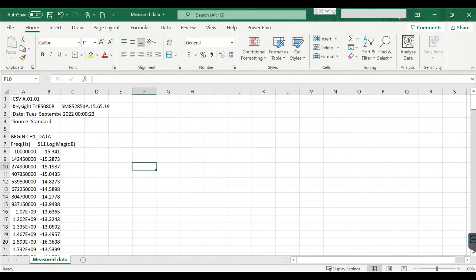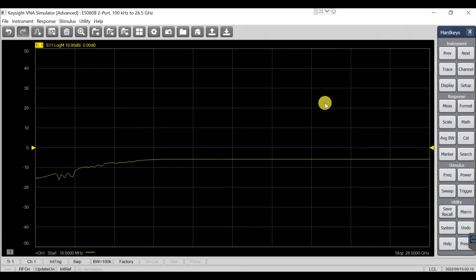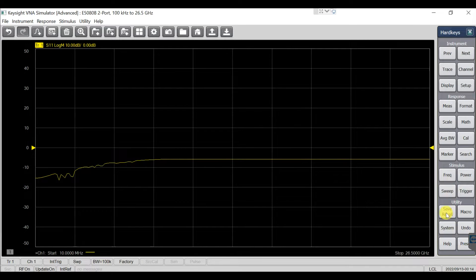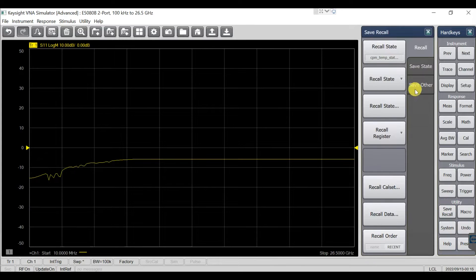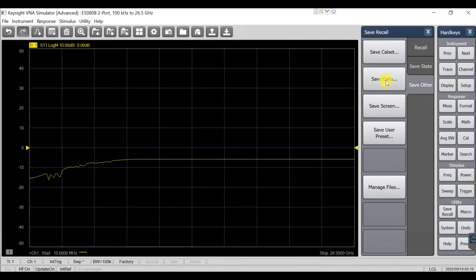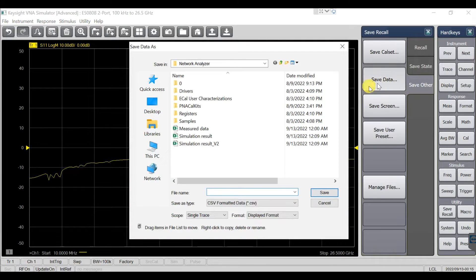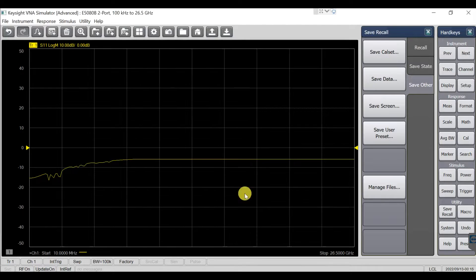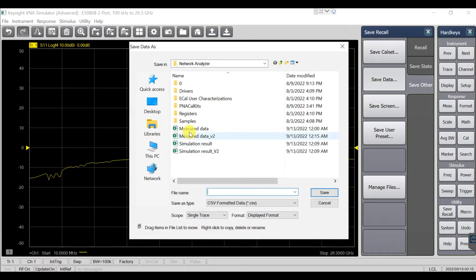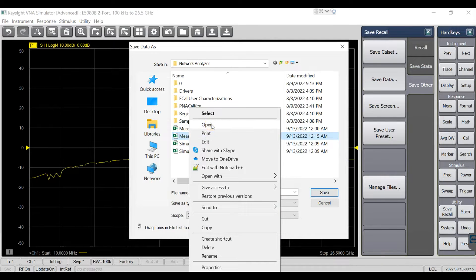I'll show you step by step. First, connect to your VNA using TeamViewer — you can install TeamViewer on your VNA. Then click on Save, go to Save and Other, click on Save Data, and save it. Let's say I save it as measured data version 2. Now I've exported the data.